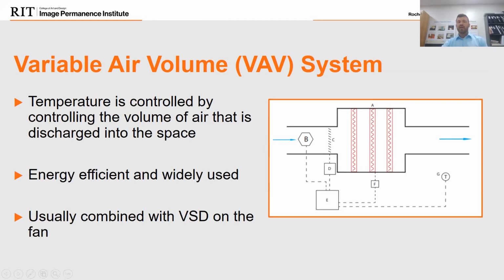The red coils there are sometimes heating coils, not present in all units, but they can be present in some. So I put them in there as an example. But you can top off a room if you need just a little more heat to a space. These can be combined with speed drives or frequency drives to really make them efficient. And these are being used more and more often as one of the more energy efficient ways to produce an environment within a collection space.